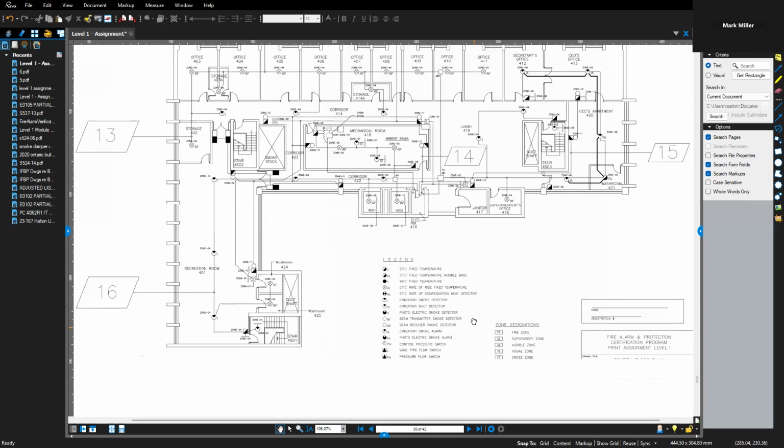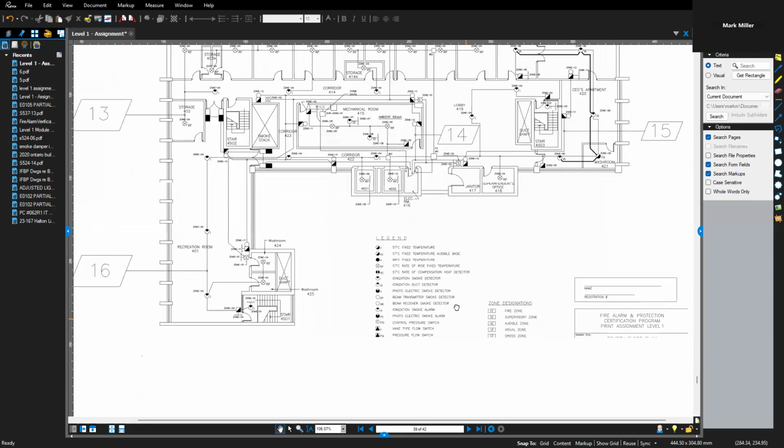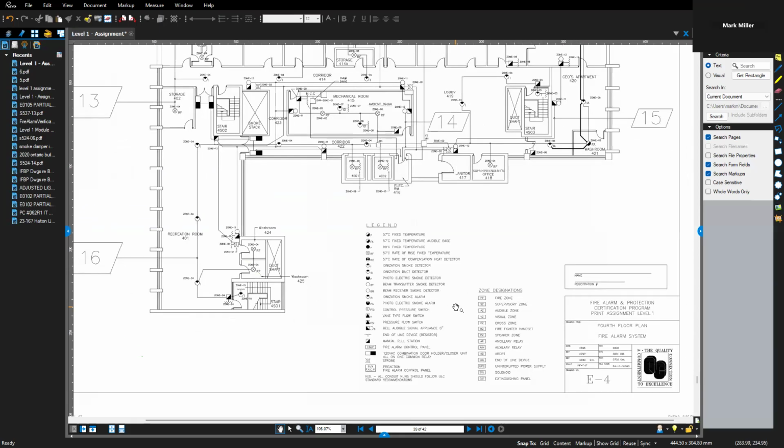But then, if it ever loads, we can see that the IA is an ionization smoke alarm, not a smoke detector. To make a smoke detector into a smoke alarm, we have to put the sounder bases in.